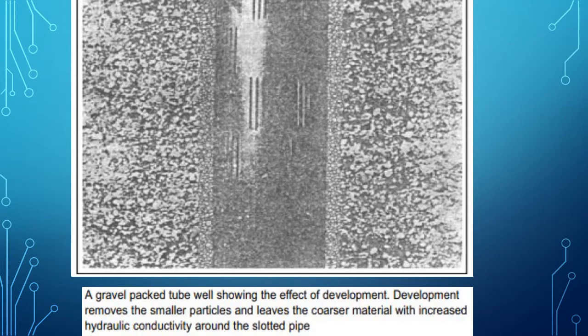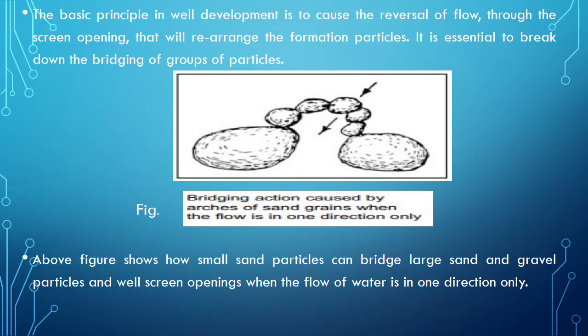The purpose of well development is to increase hydraulic conductivity, porosity, or transmissibility in the immediate vicinity of the slotted pipe or well screen, and to increase the effective radius so the yield of the well will increase after well development. The basic principle in well development is to cause the reversal of flow through the screen opening, which will rearrange the formation particles.